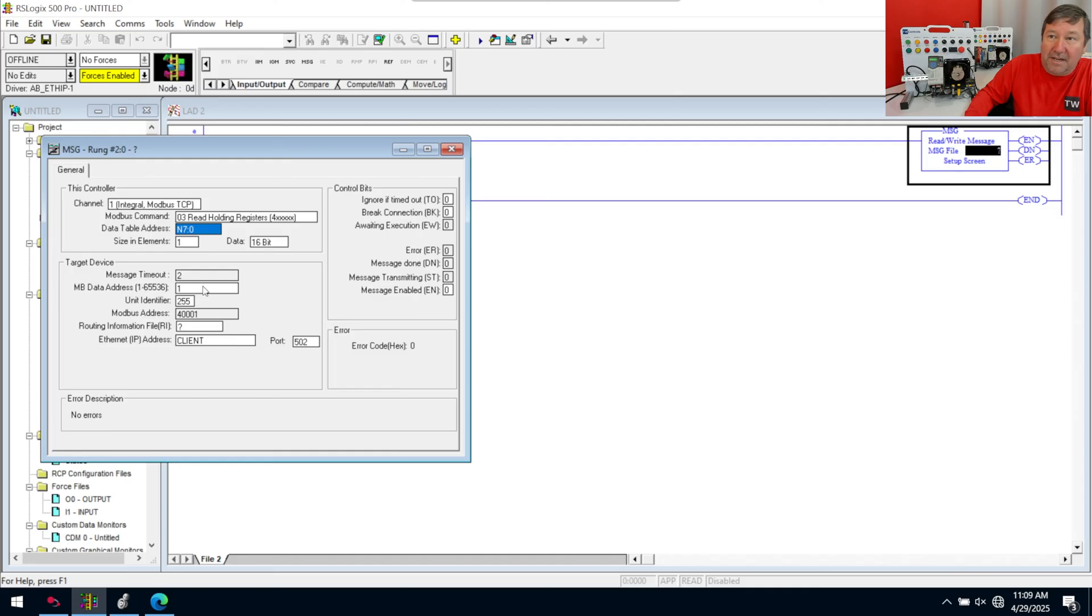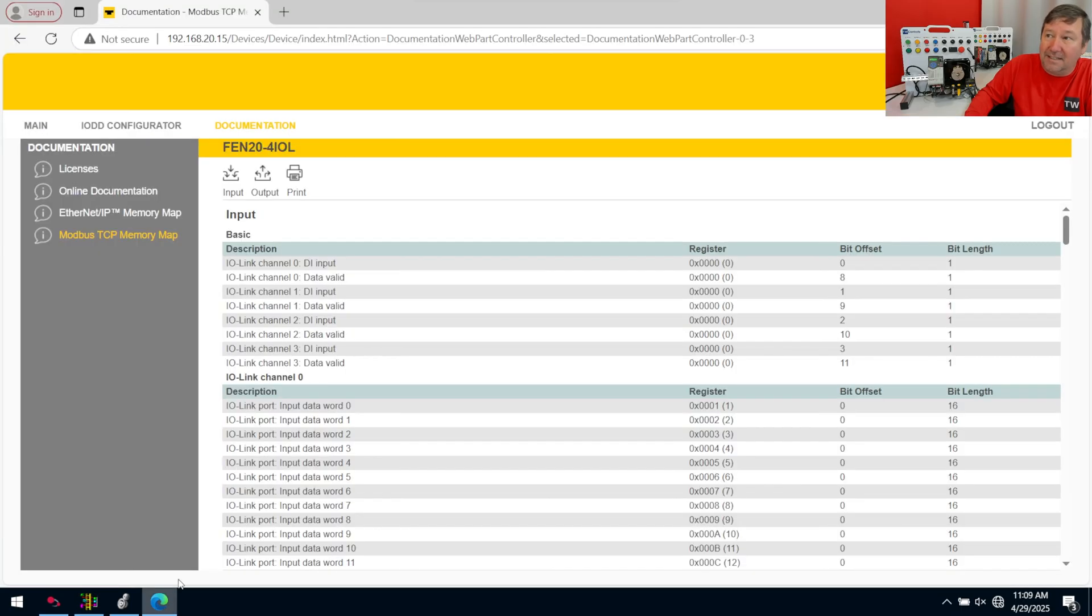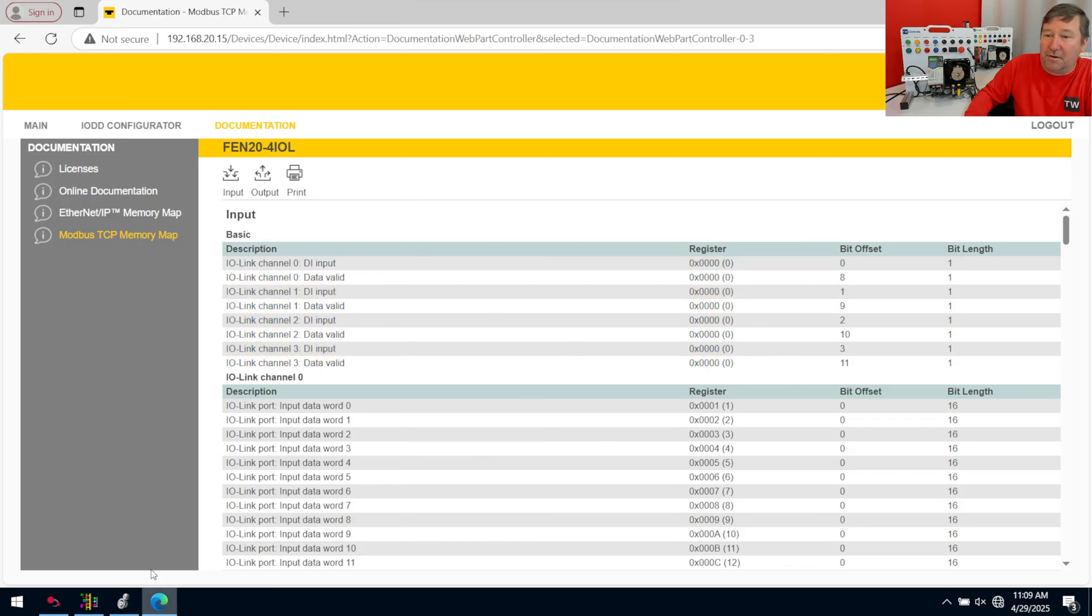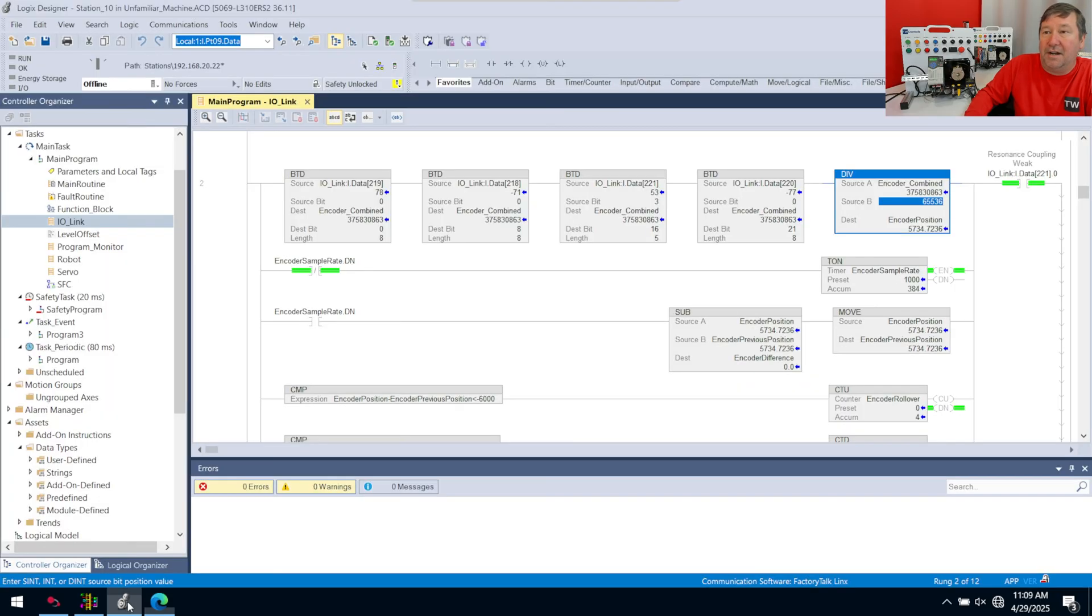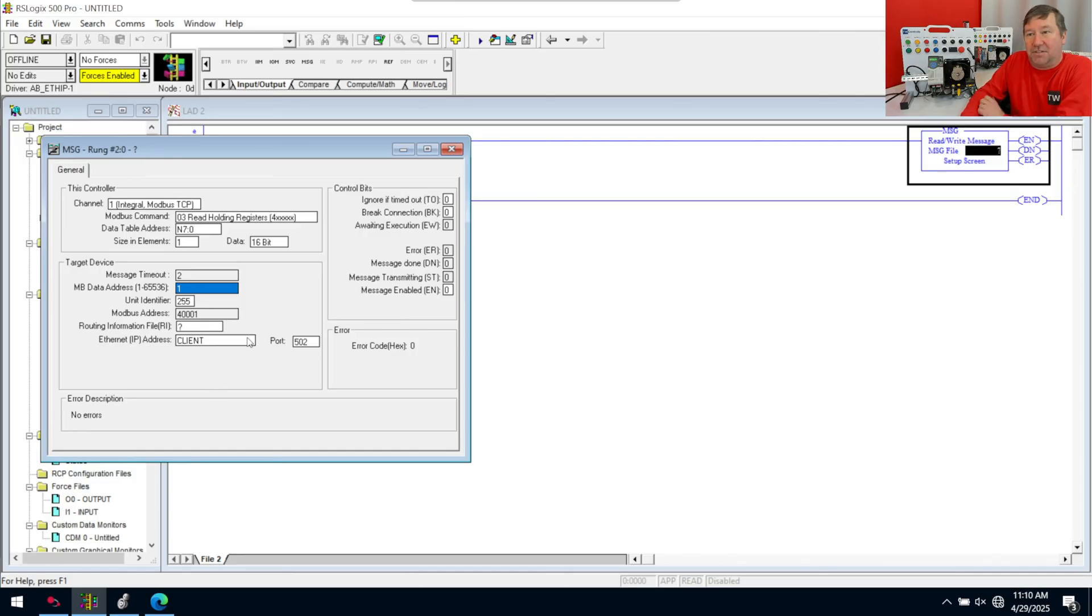This is what do you want to read out of that device. You notice in the MicroLogix, it starts at one. And here's where it gets so confusing. One in this is going to be zero in this. So all our numbers are going to be thrown off by one. And I'll be honest with you, almost every single time, really, I have to just try and find out I'm off by one.